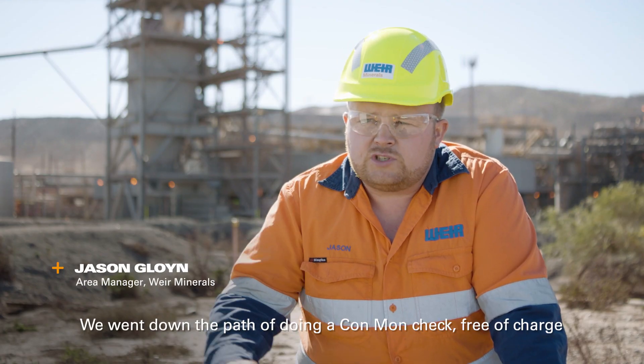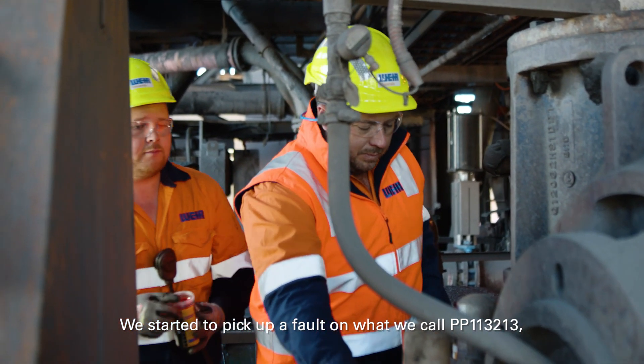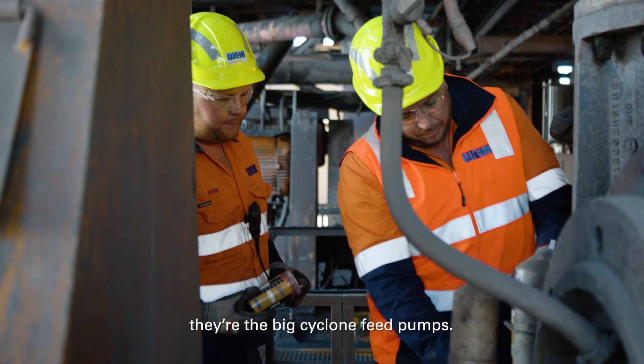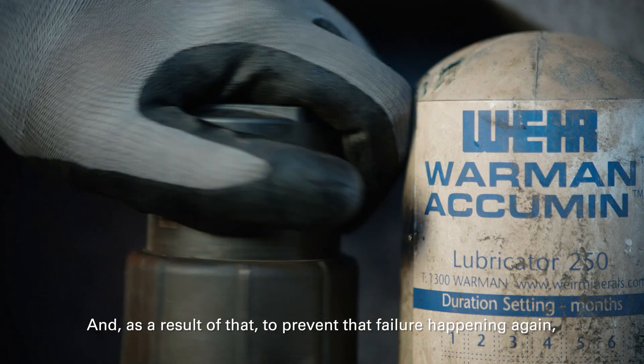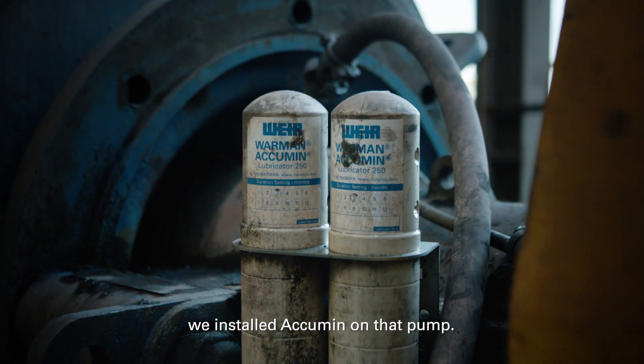We went down the path of doing a condition check free of charge. We started to pick up a fault on what we call PP113213, the big cyclone feed pumps. We identified that it was going to fail and we stopped it before the failure mode. We then carried out a rebuild on that, and as a result, to prevent that failure happening again, we installed Accumin on that pump.